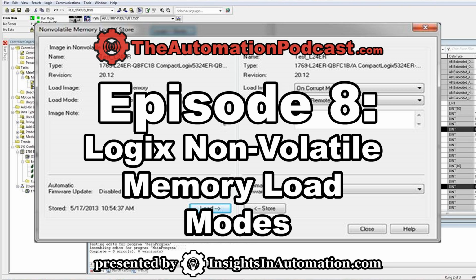Now you should notice when you do that, when you try to go online, you're going to get the note saying, hey, I got the default program loaded. The reason is we erased the processor's memory, but also removed our non-volatile memory card. So to continue with the test, go ahead and reinstall the non-volatile memory card, download program 1 to the controller, and go online and open up controller properties, open up non-volatile memory, and change the load image mode to on corrupt memory and store that program to your non-volatile memory.